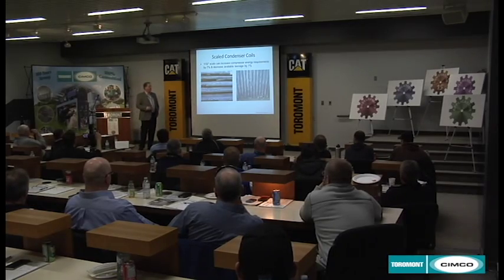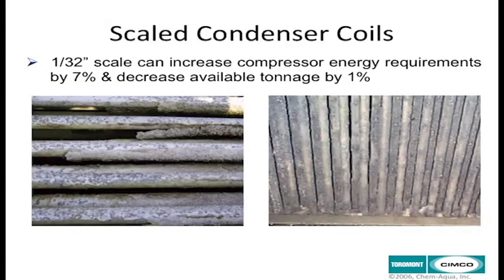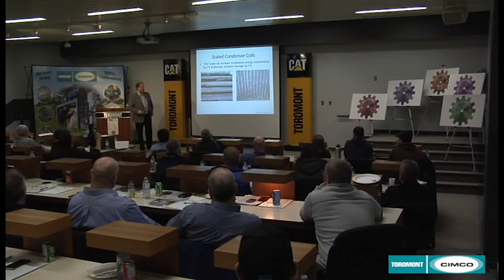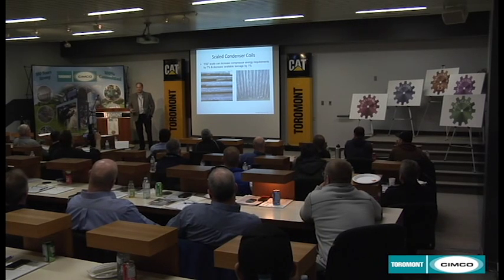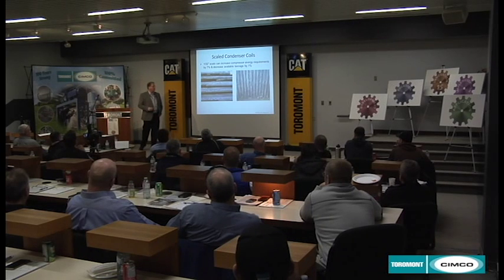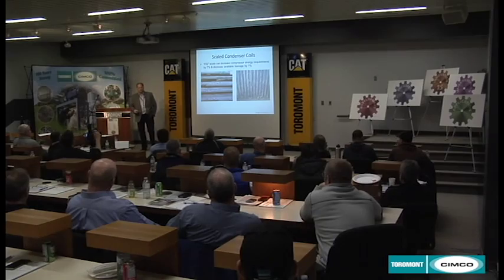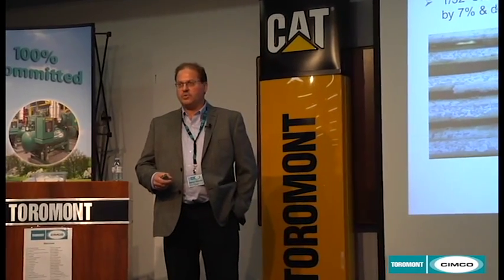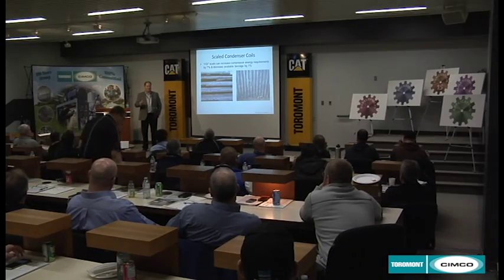A little bit about scaled condenser coils. I've seen this in an evaporative condenser. Not fun to see, not fun to clean. That's where you lose a lot of your energy costs. As you can see, 1/32 of an inch of scale increases compressor energy requirements by 7% and decreases available tonnage by 1%. That's a lot of energy cost associated with that. And 1/32 of an inch of scale is a business card. That's how thick that is.